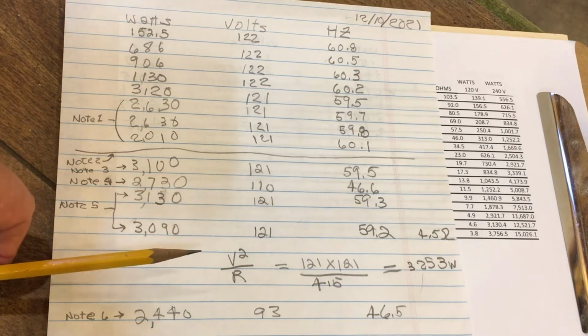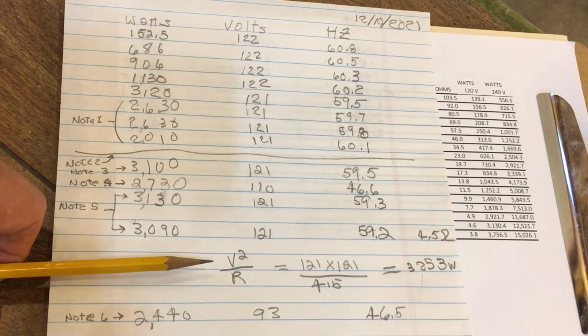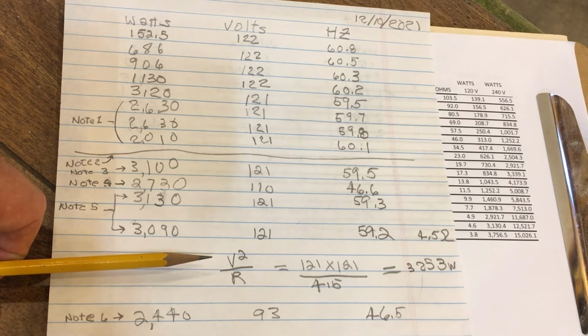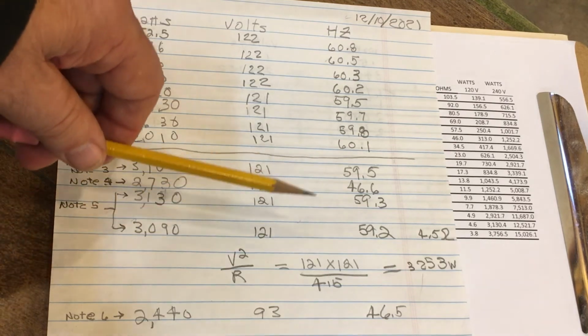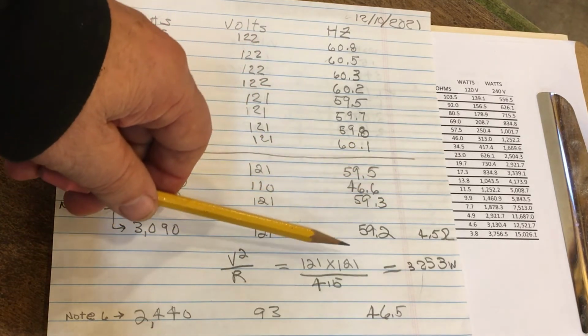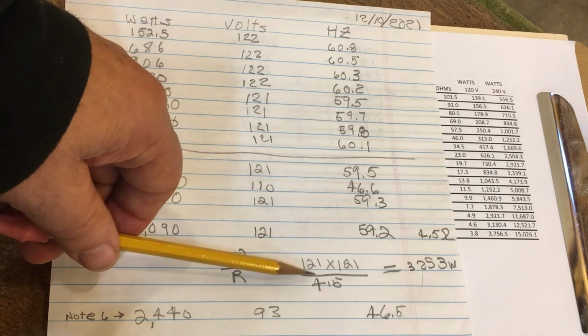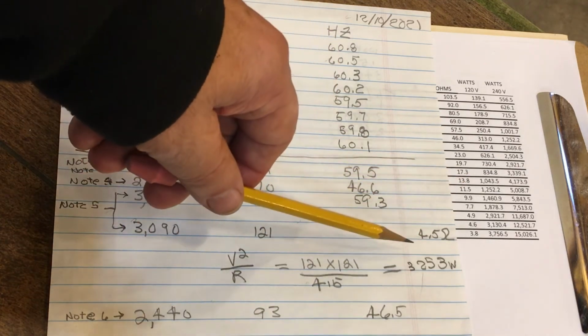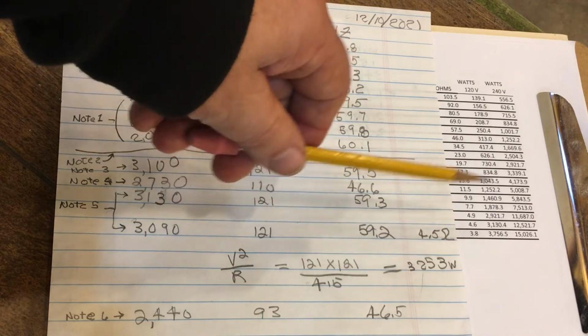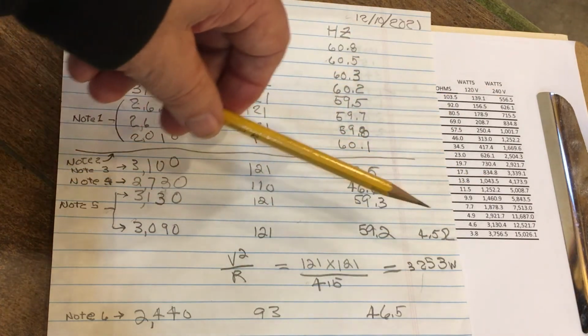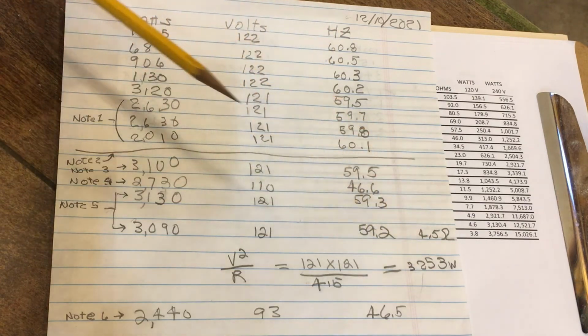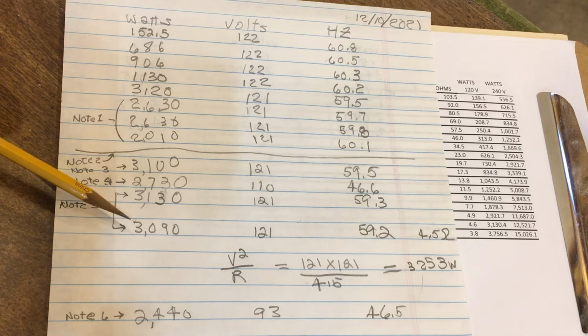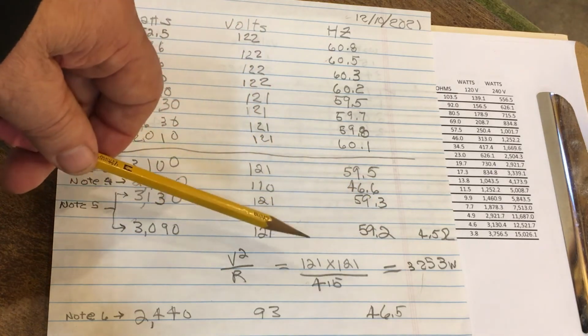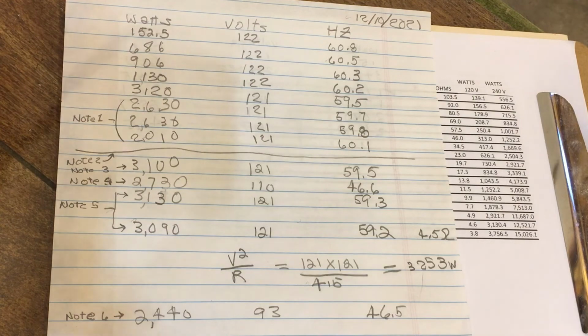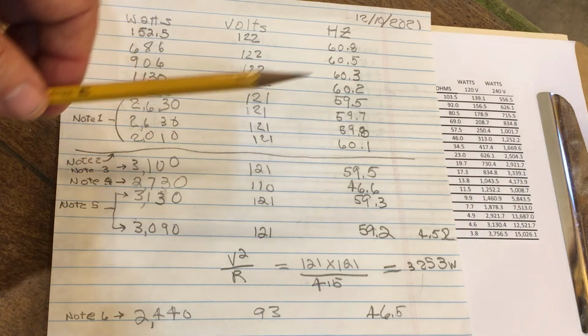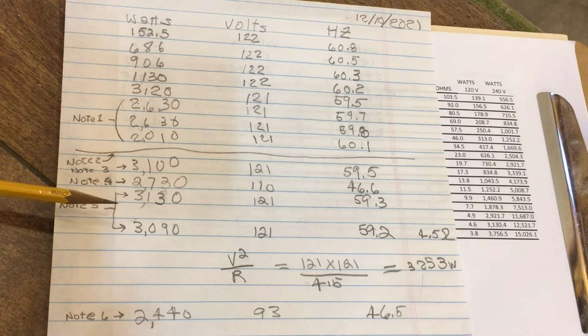At this point, by Ohm's law, V squared over R represents the power of an operating system like this. So we had 121 volts times 121, which is V squared, divided by 4.5 ohms, and that predicted a 3,253 watt load. So basically this was just a check to see if our 3,000, 3,100 watts was reasonable. It predicted a little bit higher, obviously, 253 watts or maybe 153 watts higher than the power meter.